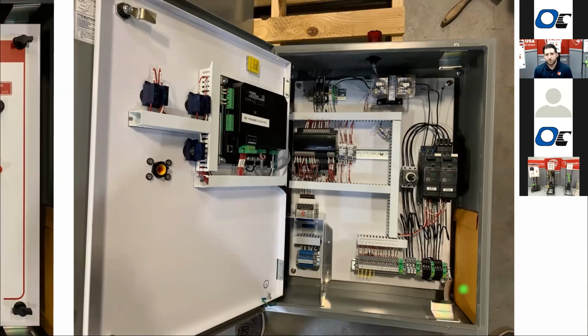All of the motor explosion-proof wiring, and all the other regular terminations, would come in over here on this side. We do use a special type of float switch when we're using intrinsically safe controls. It has gold-plated contacts so that it can get good readings with that low energy signal. Regular float switch contacts typically won't work as well. And any pressure transmitter that we would use would carry the correct UL listing as a powered device in the sump. So, special level devices to be used with the intrinsically safe controls.